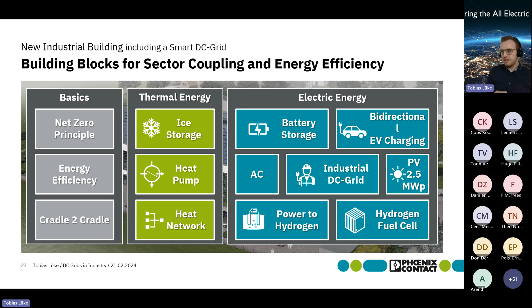The thermal energy concept is very special because we combine an ice storage with a heat pump, making the heat pump very efficient even on cold winter days. We're also connecting this building to our heat network across the whole headquarters facility. But the main focus today is the electrical energy column. The main part of the building is still powered by AC, but we implemented an industrial DC grid connected to a battery storage, which is connected to the PV on the roof, which is connected to bidirectional EV charging, and which in the future will also power hydrogen and a fuel cell.